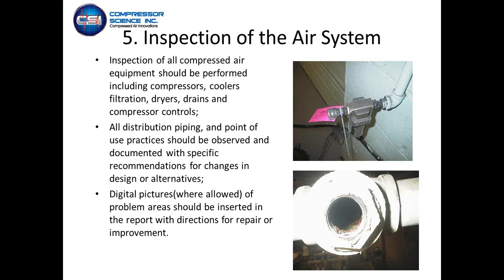Inspection of the compressed air system, really you have to look at every aspect of the air system: the compressors, the coolers, the dryers, the filtration, drains, how the compressors are being controlled, distribution piping, point of use practices, how they're using compressed air. All of it needs to be documented, and if there's any opportunity for changing any of those aspects in the compressed air system, those recommendations for changes have to be shown alternatives.